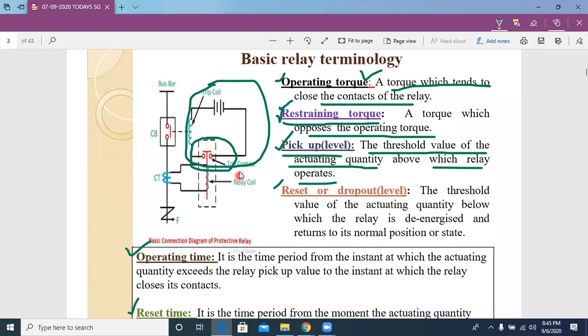Now, the next term is pickup value, or preset value. This is nothing but the threshold value of the activating quantity above which a relay operates. Here this relay coil has a preset value. If the activating quantity is current, when the current value is above the preset value, only at that condition does this relay coil produce a magnetic field, that means magnetic torque capable of closing the contacts. That value we call the pickup value.